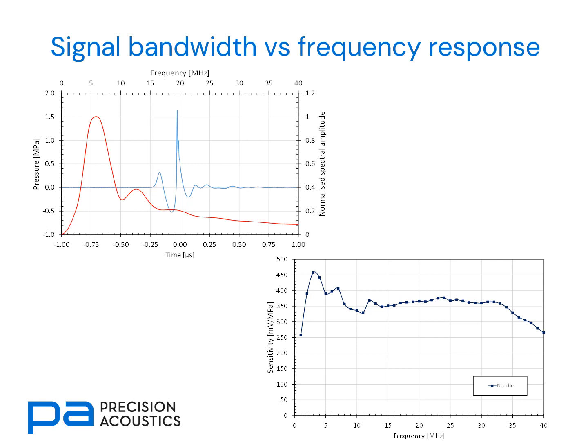Were we to look at a needle hydrophone, this has got less variation, but in the range from about 3 to 10 megahertz — where there is a lot of energy in the signal — there's still quite a lot of variation. If we'd like our hydrophone voltage to be a very good representation of the pressure field, having something with a very smooth response as a function of frequency, such as the membrane hydrophone shown here, would be a really good choice.